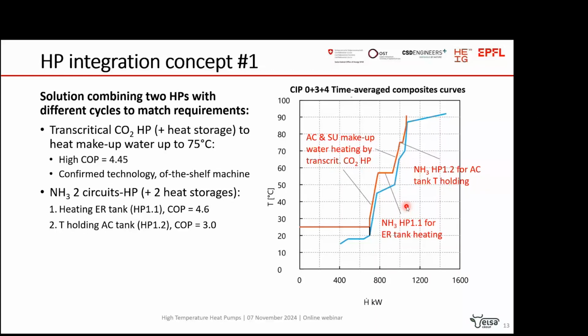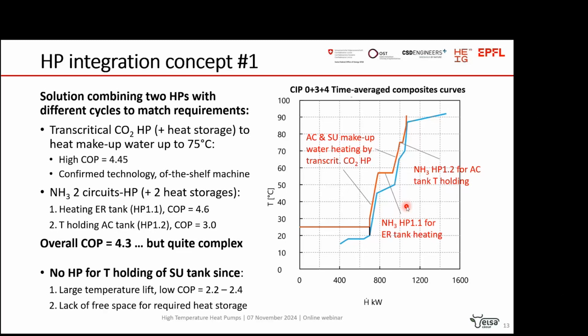So maybe it's not so useful. But overall, we have a COP of 4.3, which is good but quite complex. The reason we leave this away, or don't have a heat pump, is that the temperature difference is quite large and the COP would be low. And if we install the first 2 heat pumps, which have a higher COP, we won't have enough free space for the required heat storage for this additional heat pump.